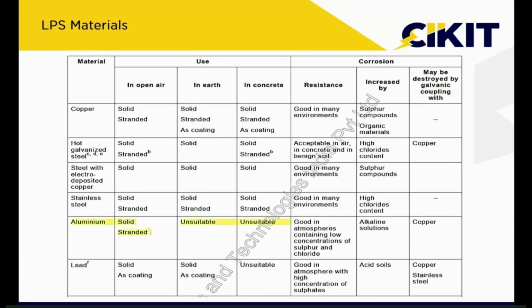The standard has highlighted that we can use different materials for the lightning protection system. We can use copper, hot dip galvanized steel, stainless steel, or aluminum. The most important point to be noted is galvanic corrosion. Normal corrosion happens when we expose iron material to the normal environment, but galvanic corrosion is due to the chemical reaction between two dissimilar materials. If I connect aluminum and copper together, because of the difference in chemical properties, the aluminum will corrode much faster than the other material. This type of corrosion is called galvanic corrosion.